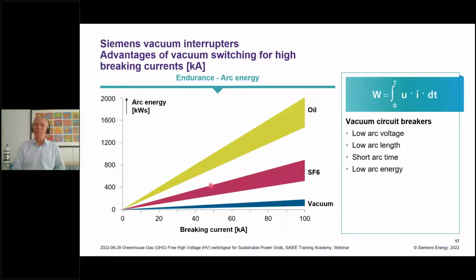Another big benefit of the vacuum interrupting technology you see here. Horizontally, you see the breaking current up to 100 kA, and vertically, the arc energy which is generated during switching. Let's have a look at, for example, 40 kA. You see that an oil breaker had around 800 kWs generated in the past. SF6 had about 50% of that, and you see that a vacuum interrupter has up to again 10 times lower arc energy generated. Why is that so?